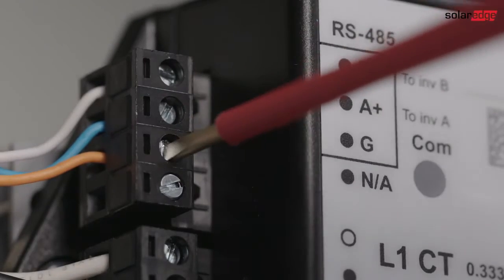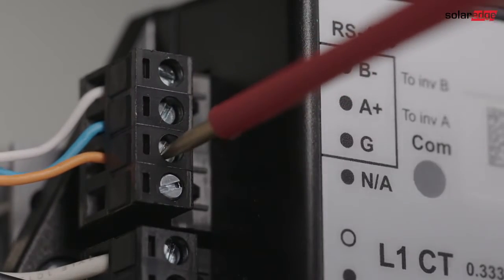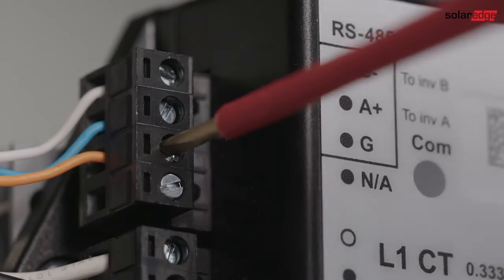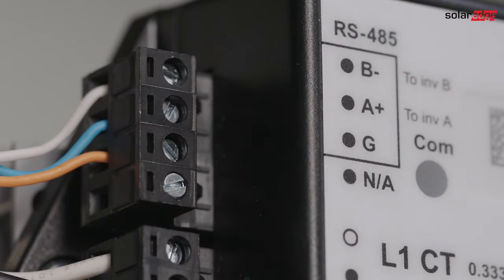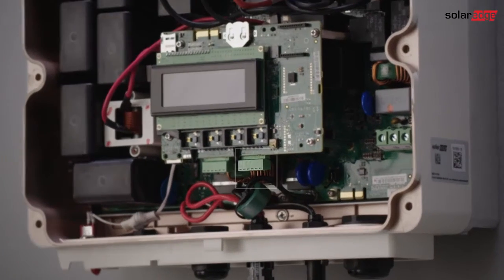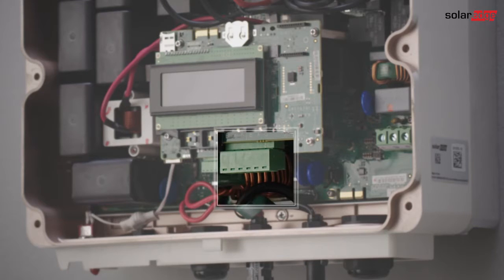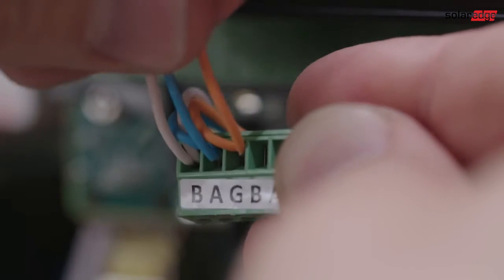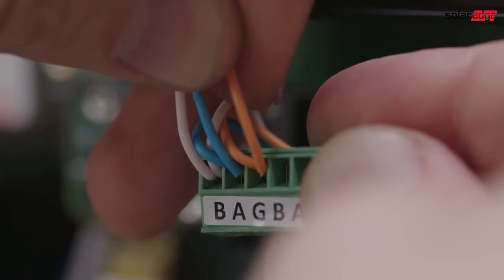Next up is the connection of the RS485 bus. We recommend using a Cat5 cable. A twisted pair must be used for terminals B and A between meter and inverter. We recommend using the white and blue wires. For the G terminal, any other wire can be used. We recommend using orange. In a StorEdge interface system, the meter and interface connect to the same inverter RS485 terminals.